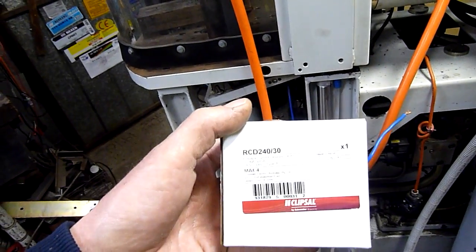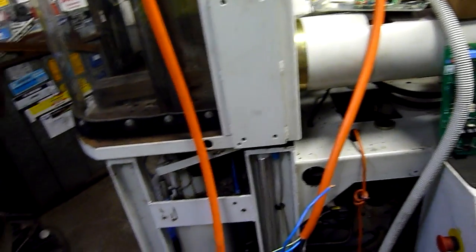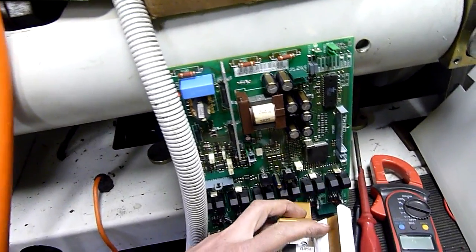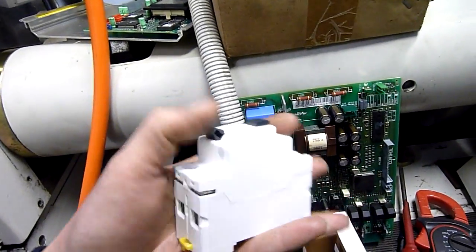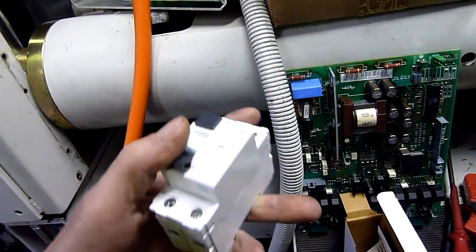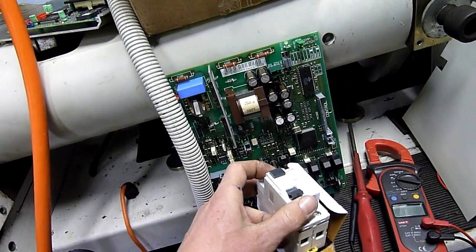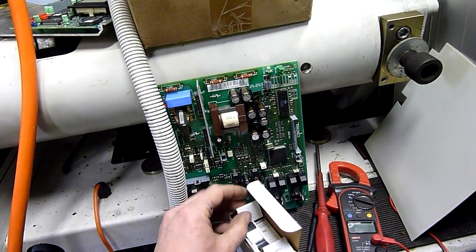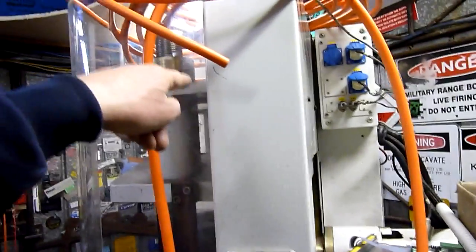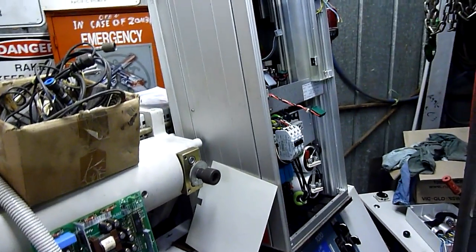I was hoping I could get a sparky to install this 40 amp breaker come RCD, a safety switch that's mandatory on all main electrical installations in Australia. That was thirty two dollars. It's a shame if I can't use it. It's essentially a 30 milliamp ground fault interrupter, earth leakage breaker, safety switch, RCD, residual current device, whatever you like to call it. I was even debating not using one, but if we're going to branch off from the main feed from the meter, legally it has to have one. So I'd have this installed out here and a regular 40 amp breaker in the panel on the house, so that way if I do get moisture in something or cock something up, I'm not walking up to the house just to turn it back on again because that gets old real fast, especially when you've got an air conditioner with a tiny drop of moisture in the relay or the thermostat.